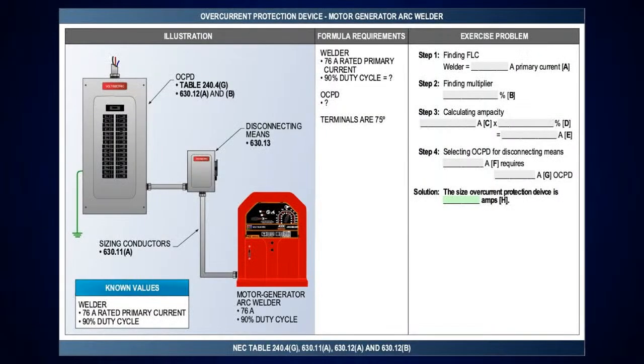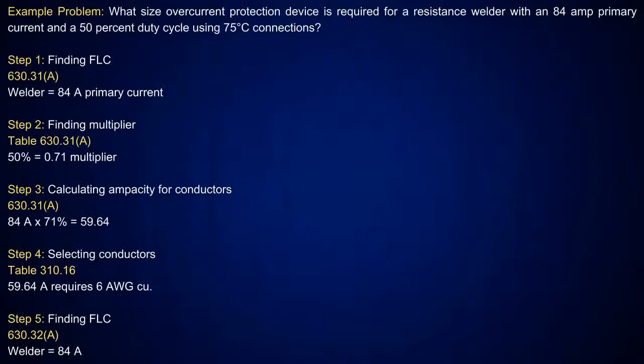Okay? And then when you come over here, you pick up a motor generator arc welder. So we got you an easy calculation. You know the welder, looking at this, it's 76 amps. And we're just going to get the percentage. So I'm going to look at 630.12 A and B there. You're going to know to take it at 200%. Don't exceed the calculated value and drop down to the next standard size for your homework next week.